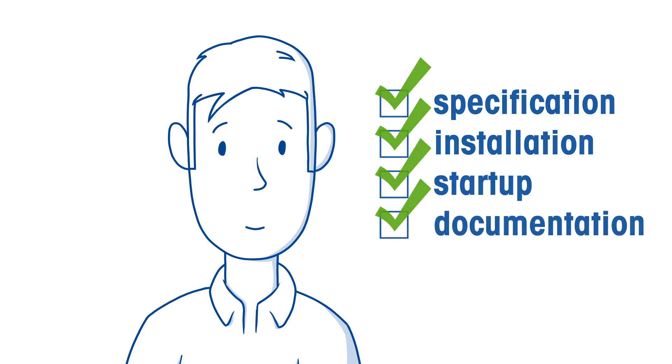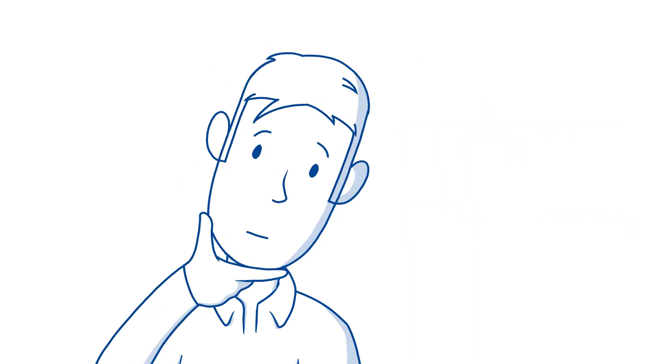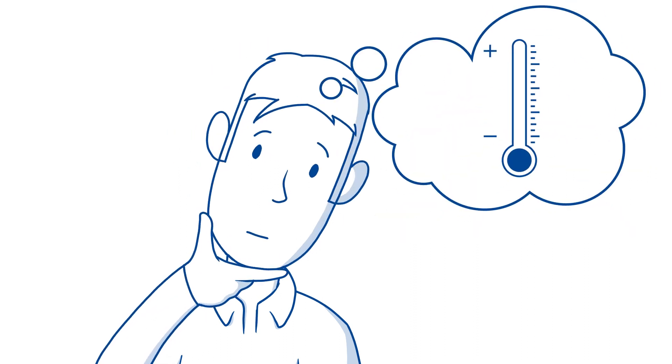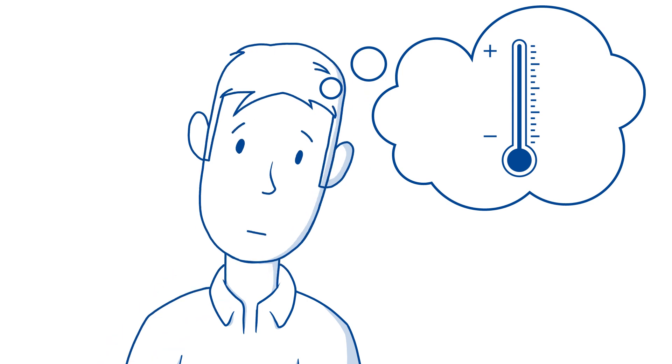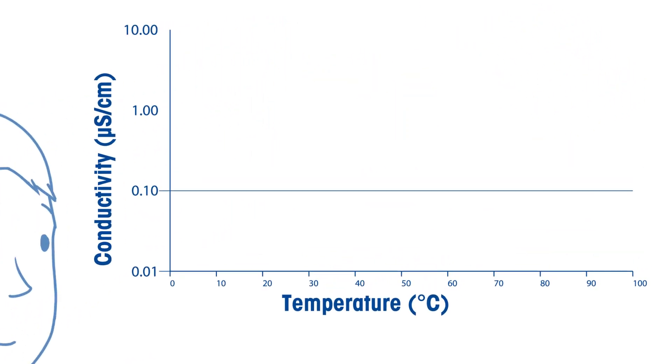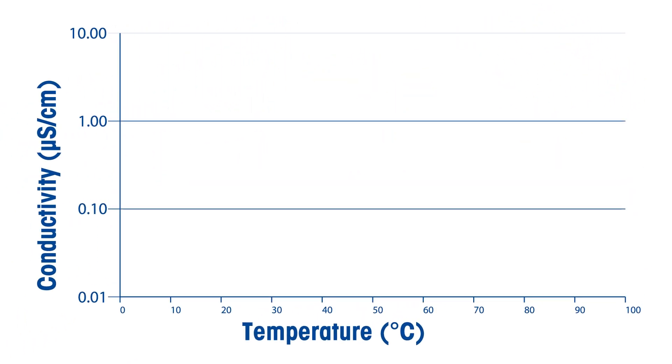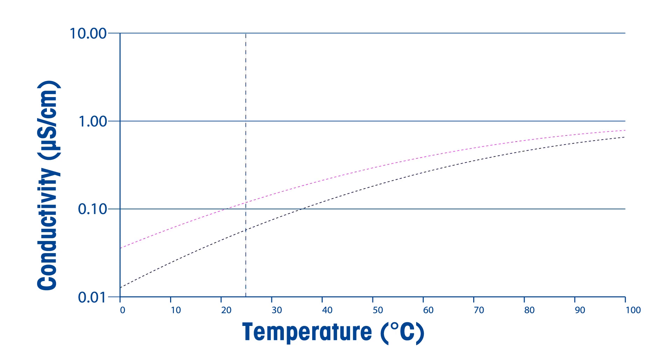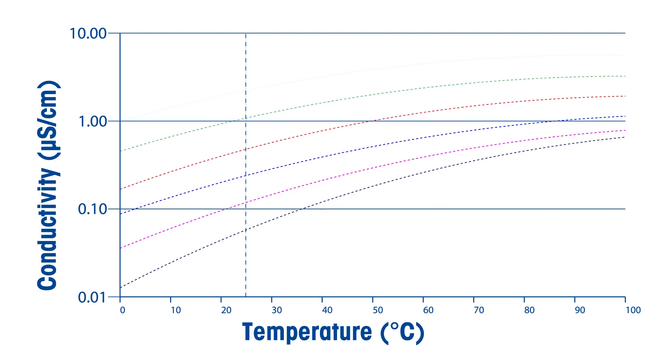Now let's talk about how temperature compensation factors into accurate conductivity measurements. Water purity specifications always reference conductivity values to 25 degrees Celsius. Conductivity can vary as much as 5% of its value per degree change and must be compensated to ensure accurate measurement.